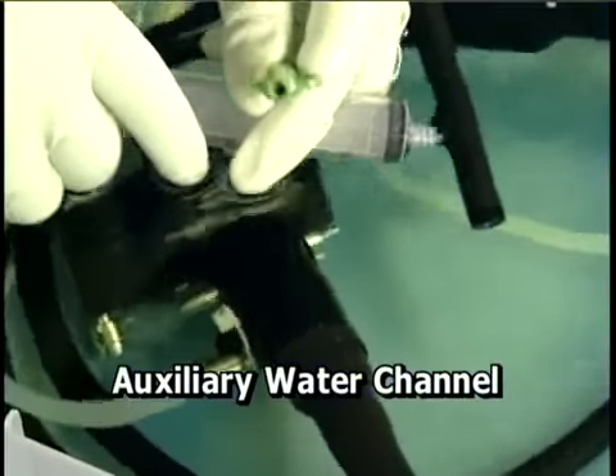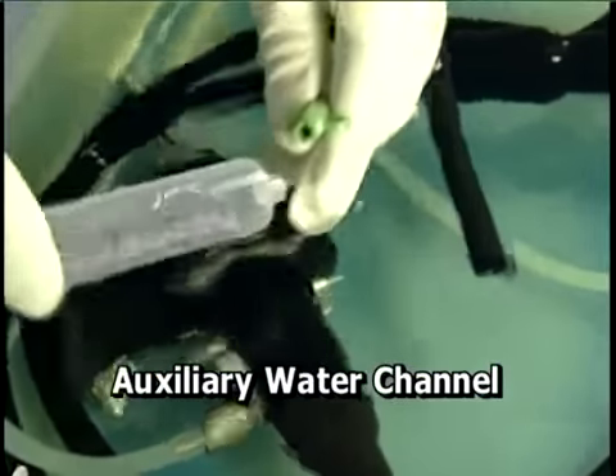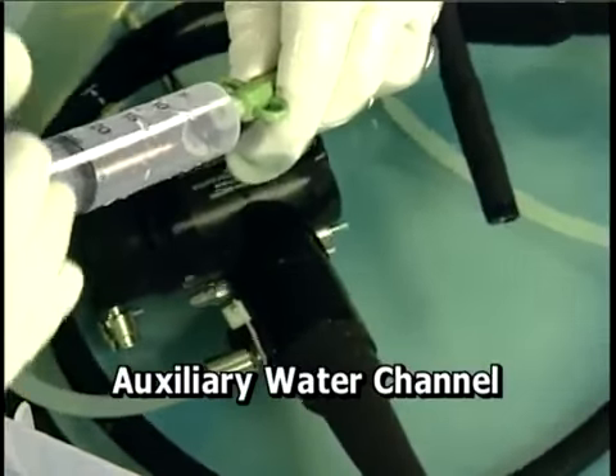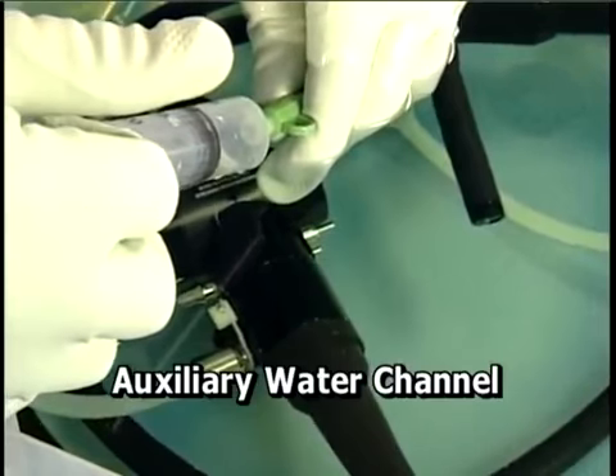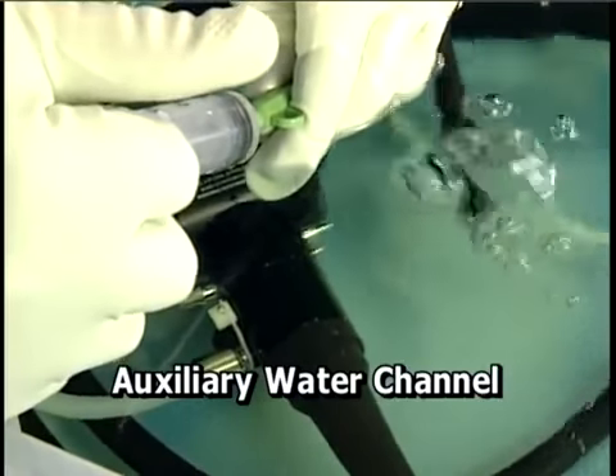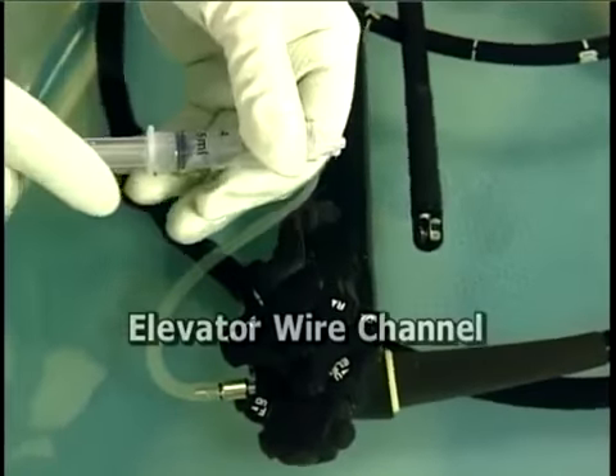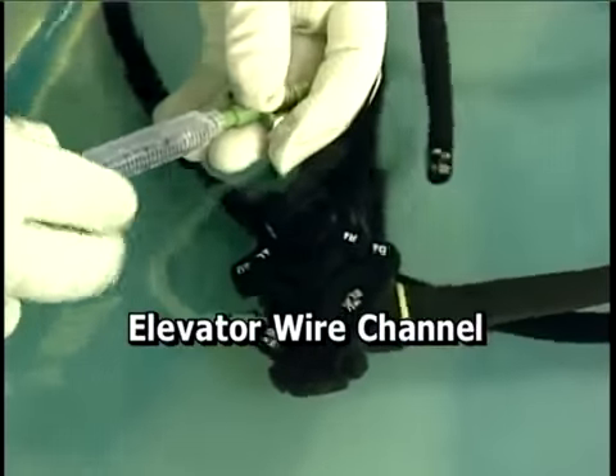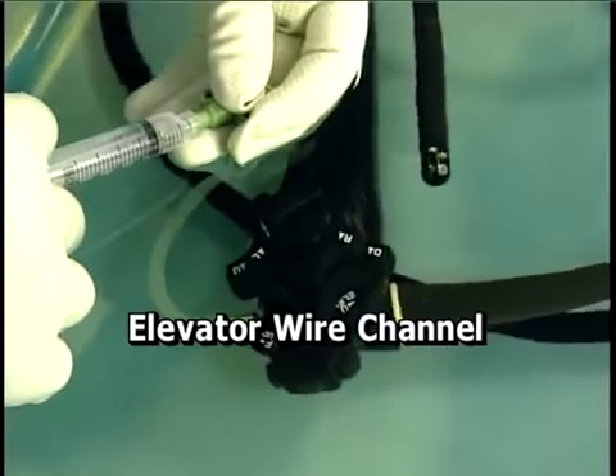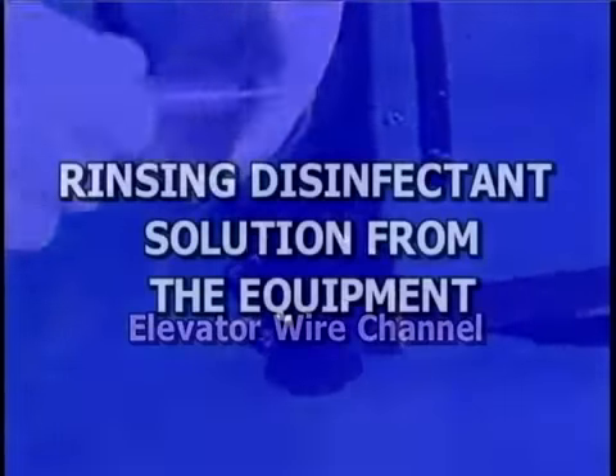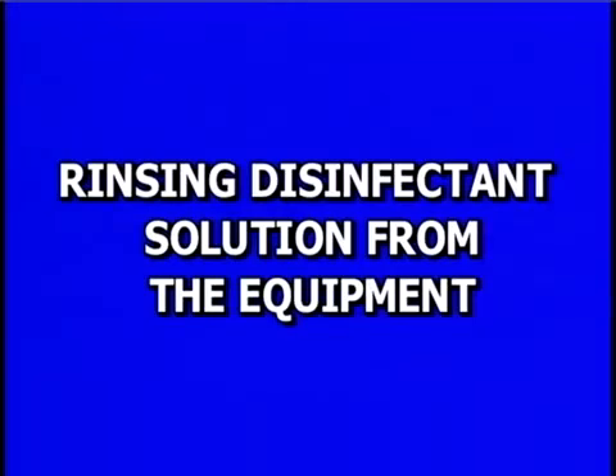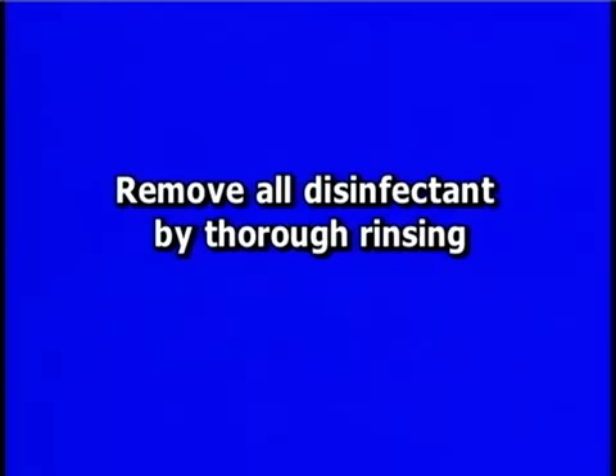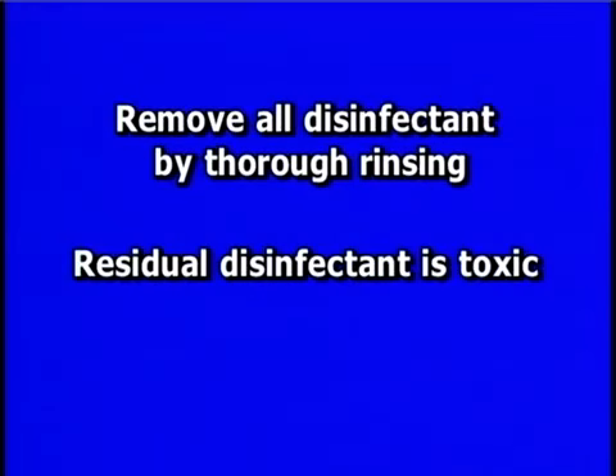If you are reprocessing an endoscope with a special channel, use a syringe to inject air into the auxiliary water channel, expelling disinfectant solution from this channel as well. If you are reprocessing a duodenoscope, inject air to expel disinfectant from the elevator wire channel. Now that all of the channels have been emptied of disinfectant, the next step is rinsing. It is very important to remove all disinfectant solution from the endoscope. Residual disinfectant is toxic and can injure the next patient examined with the endoscope.